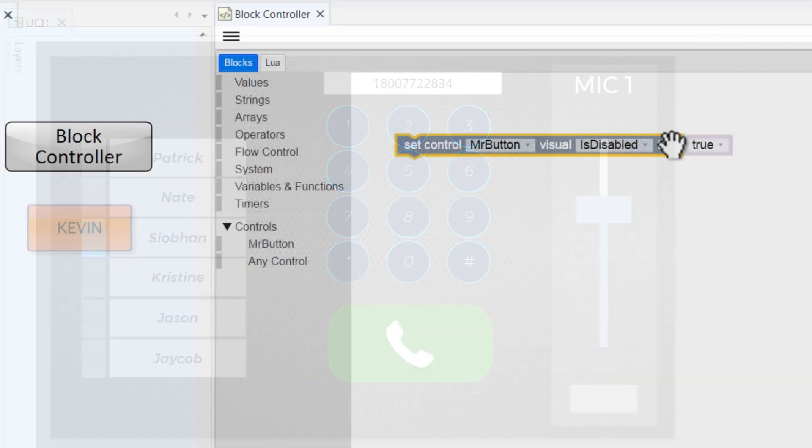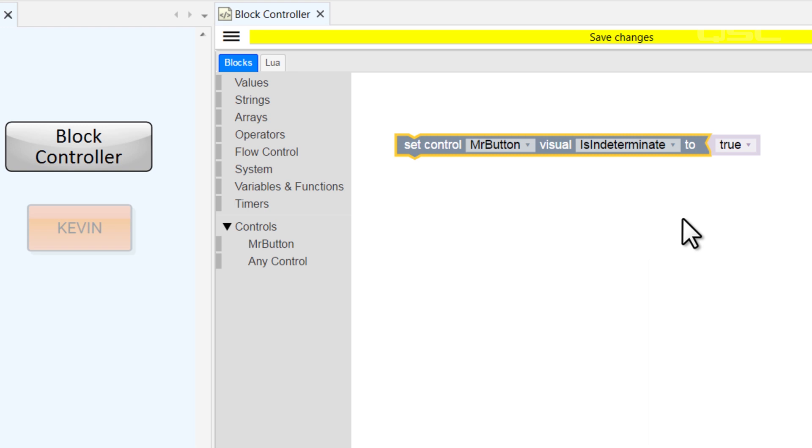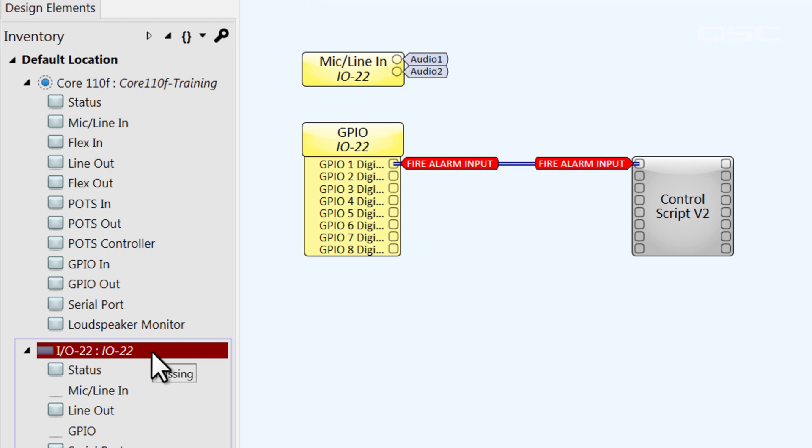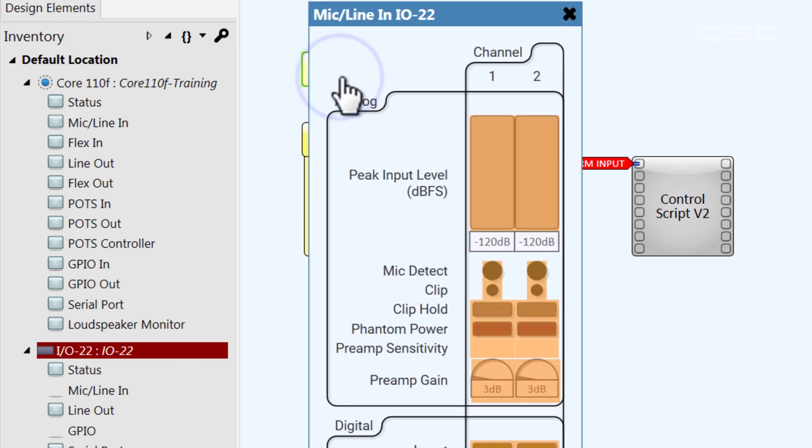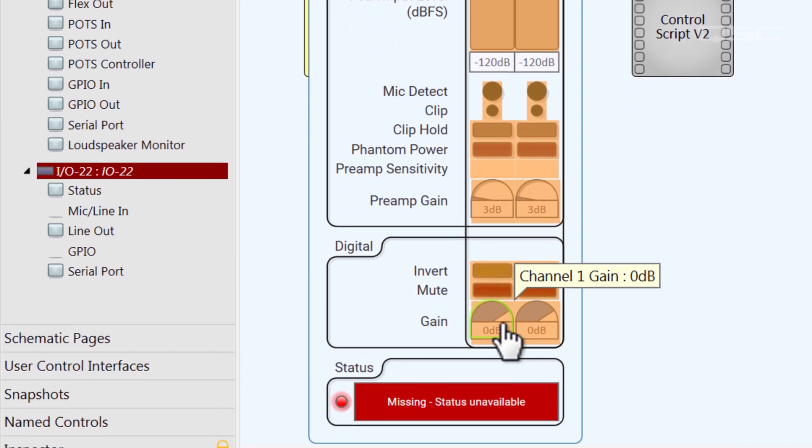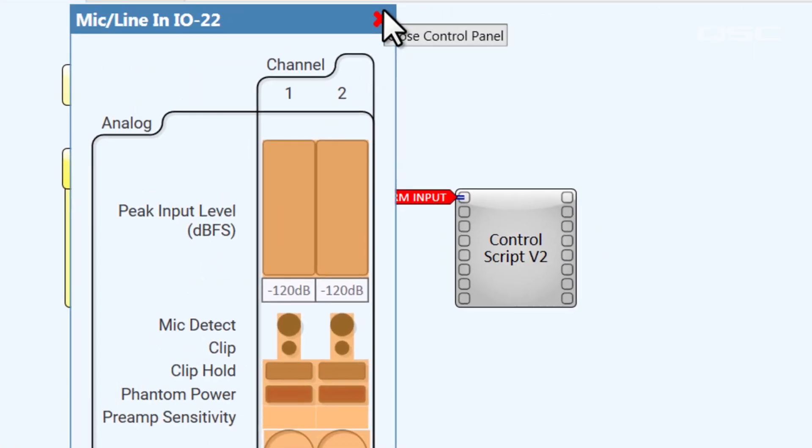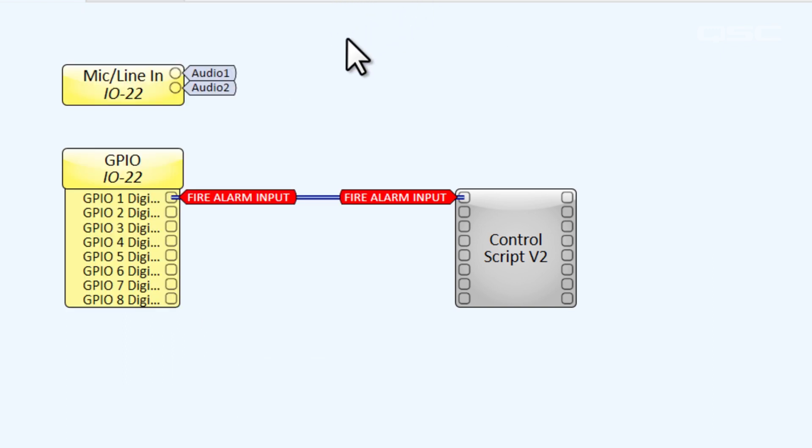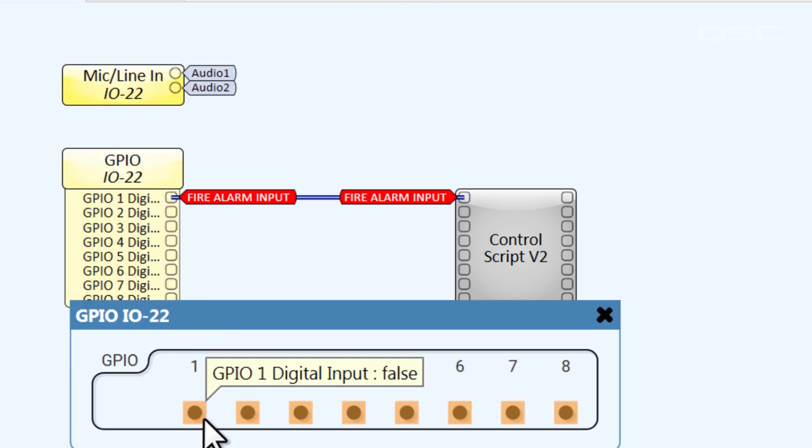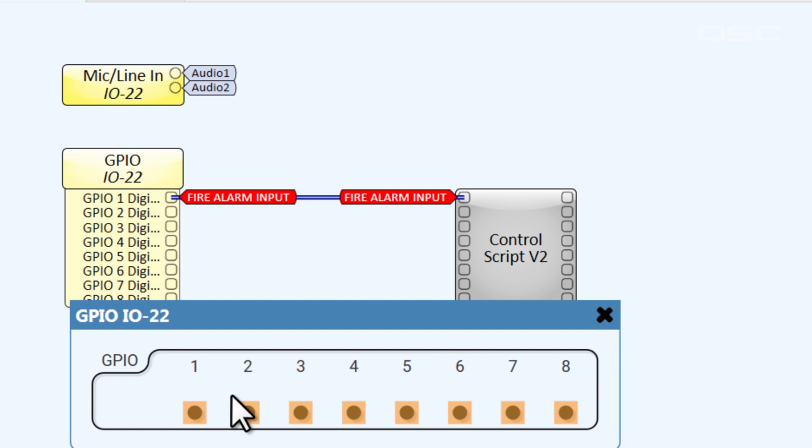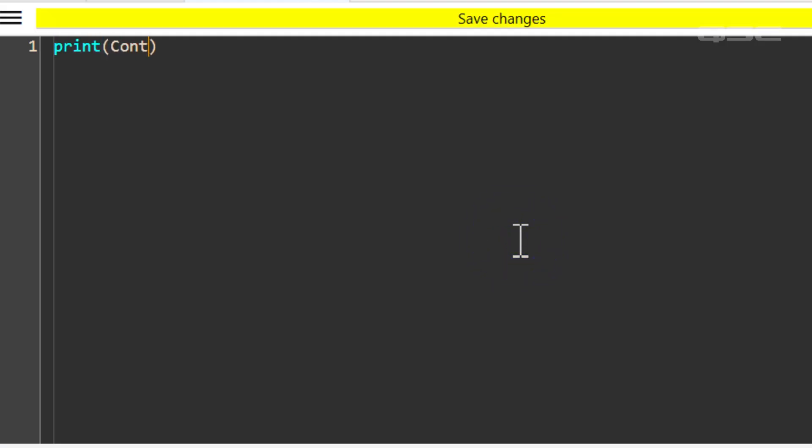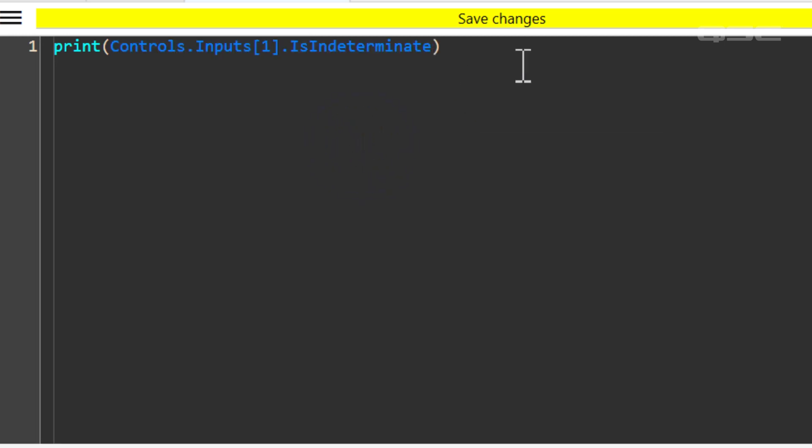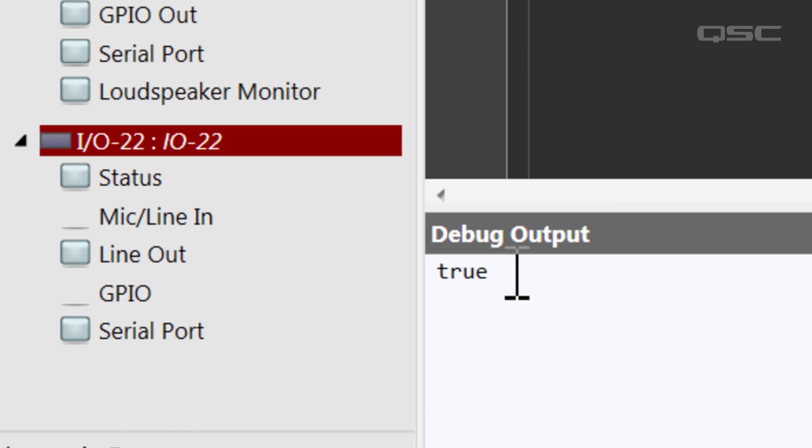The .isIndeterminant property is another example of a disabled button, although you're less likely to force this state upon a control as you are to read this property from a control. When a peripheral device is not connected to the network, for instance, its controls take on this faded red color, which is the result of being indeterminant. It means the system cannot determine the connection between the control and its parent device, and thus it is indeterminant. Let's say you're monitoring a fire alarm contact closure on an I.O. frame. You could monitor both the control's value for any sign of a fire alarm, as well as the .isIndeterminant property. Because if this property becomes true, then you know you no longer have a connection to that device, which means your fire alarm system won't work.